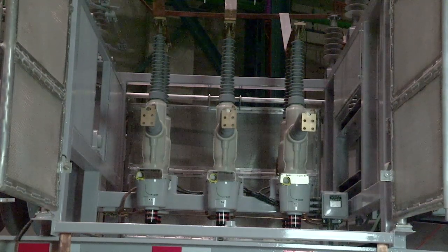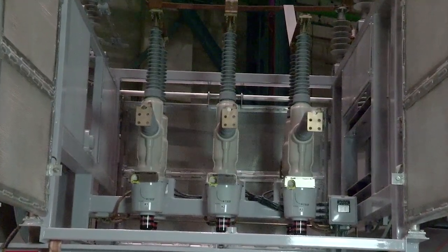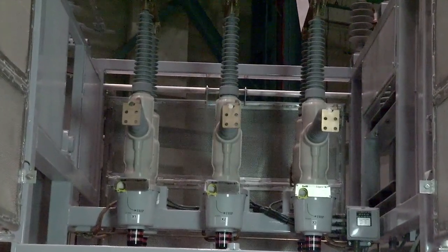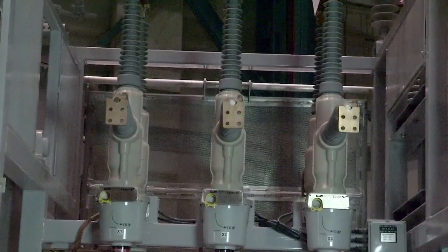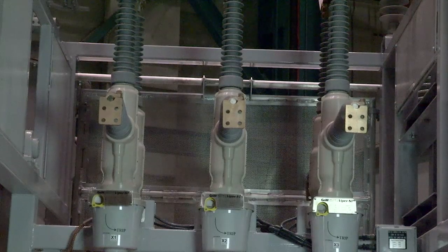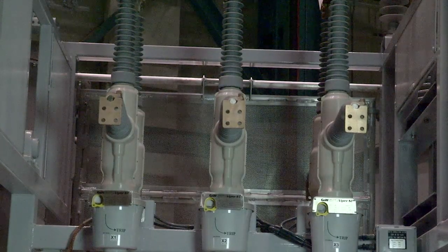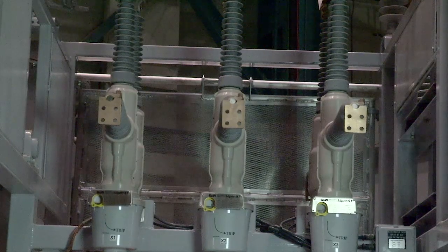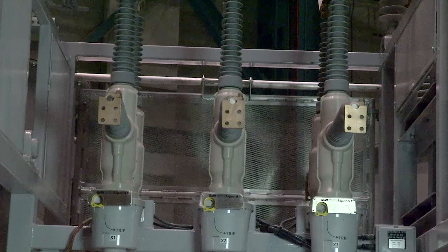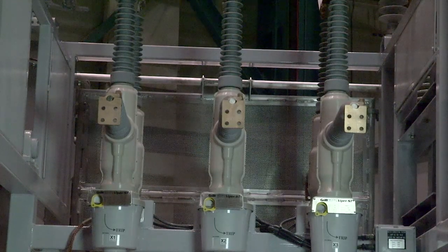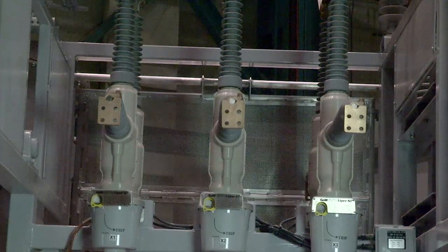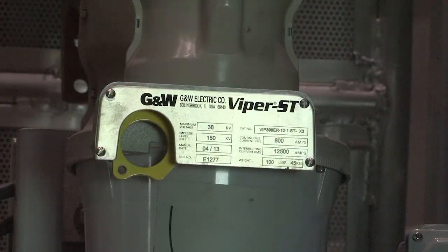Now, a few things that are really good with these reclosers, as opposed to the typical L type, are that the interrupting rating of these is 12,500 amps, as opposed to the typical L type, which is 4,000 amps. These also have a lot higher rating, 800 amps. And as far as selecting the curves, they're a lot more versatile for choosing what to pick for coordination downstream. So here's another shot of the tag that's on the recloser itself. You can see that there's the 800 continuous amps that are allowable on this recloser, as well as the interrupting current of 12,500 amps.